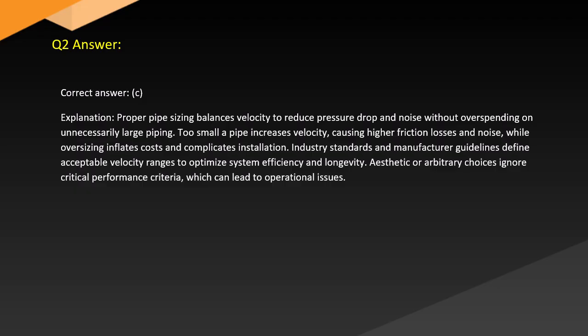Proper pipe sizing balances velocity to reduce pressure drop and noise without overspending on unnecessarily large piping. Too small a pipe increases velocity, causing higher friction losses and noise, while oversizing inflates costs and complicates installation. Industry standards and manufacturer guidelines define acceptable velocity ranges to optimize system efficiency and longevity. Aesthetic or arbitrary choices ignore critical performance criteria, which can lead to operational issues.